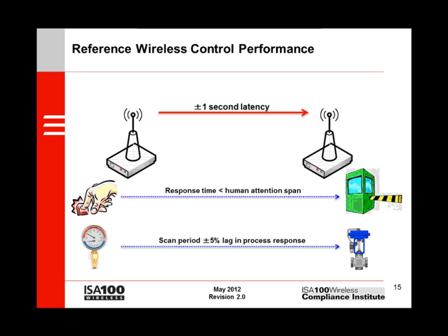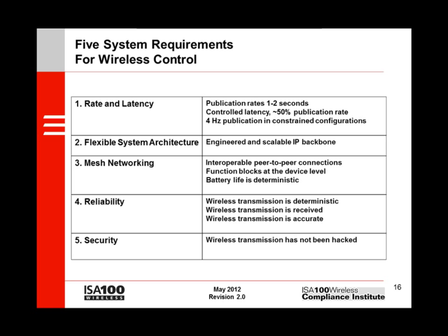For example, one commonly asked question is, do we need to actually transmit data every scan, even if the data hasn't changed? The answer, of course, depends on the application. But at the end of the day, control systems go into a failure state when data is uncertain. For this reason, you'll find that most ISA-100 control solutions are optimized to transmit data each interval. In this table, we identify five key requirements for wireless controls. First, we've already discussed sampling rates and latency. For control, you need high confidence that messages will be transmitted on time. We list one-to-two-second latency as a baseline target for control to support human-machine interaction.